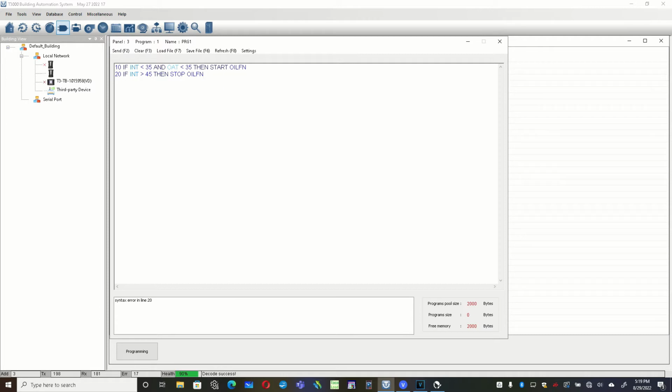In this case, if we're gonna fire this oil burner, it takes several minutes for the heat exchanger to warm up, especially if it's only 35 in there. And we need to let that thing run a while, get all the moisture out of it, and it takes several minutes to reach efficiency. So if it fires, we're gonna run the warehouse up to 45 and then it'll stop. And then it's gonna be quite a while till the heat comes back on again.